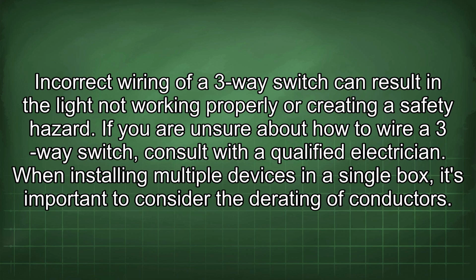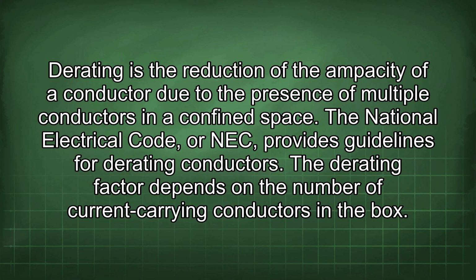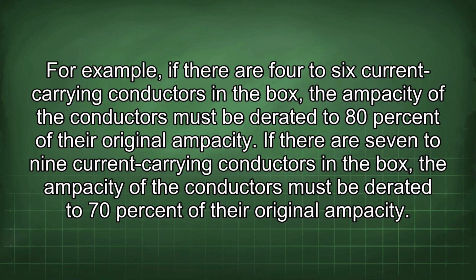When installing multiple devices in a single box, it's important to consider the derating of conductors. Derating is the reduction of the ampacity of a conductor due to the presence of multiple conductors in a confined space. The National Electrical Code, or NEC, provides guidelines for derating conductors. The derating factor depends on the number of current-carrying conductors in the box. For example, if there are 4 to 6 current-carrying conductors in the box, the ampacity of the conductors must be derated to 80% of their original ampacity.